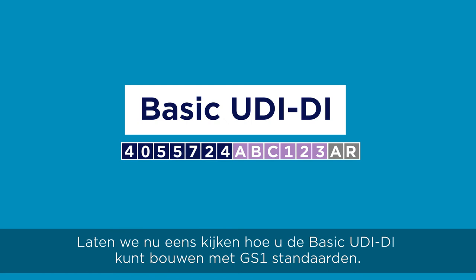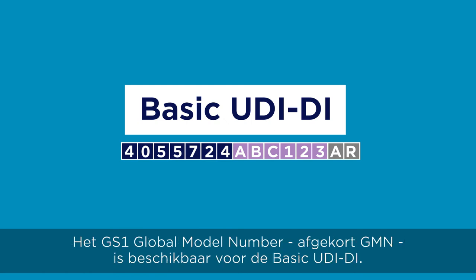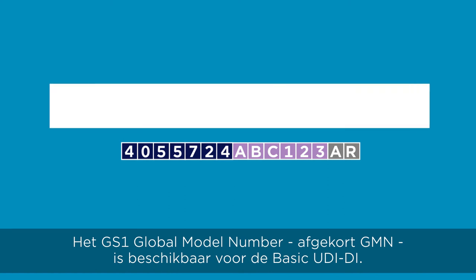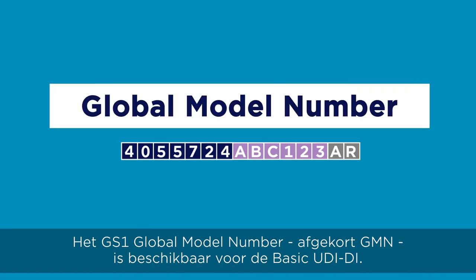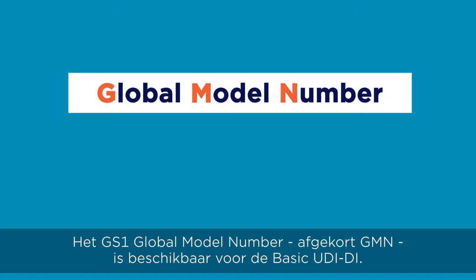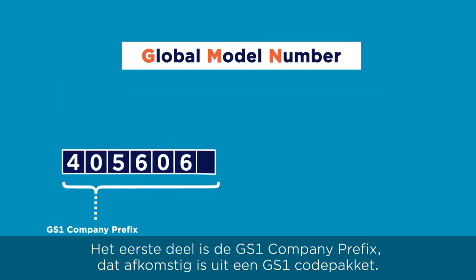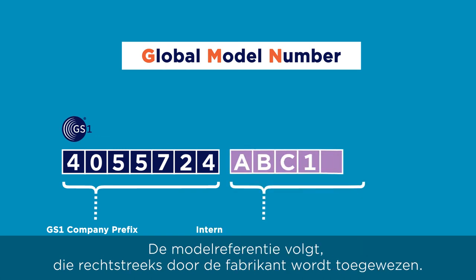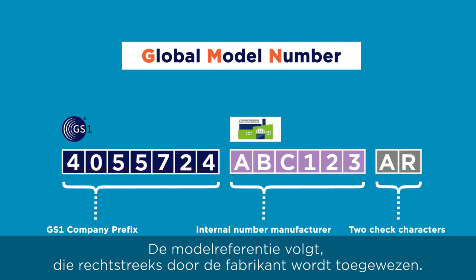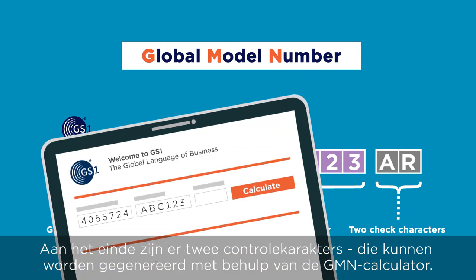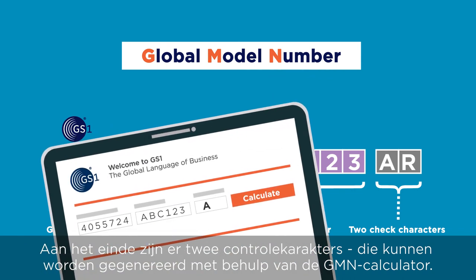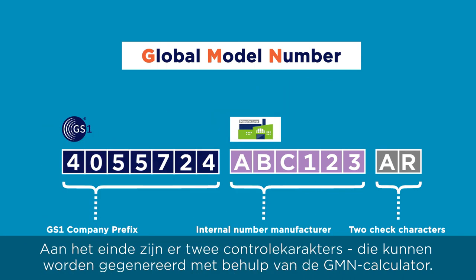Now let's see how you can build the basic UDI-DI with GS1 standards. The GS1 global model number, abbreviated GMN, is a GS1 key which allows the creation of a basic UDI-DI. The first part is the GS1 company prefix, which is uniquely assigned to a GS1 member company. The manufacturer internal number for that group of devices follows, which is assigned directly by the manufacturer. At the end of the GMN there are two check characters, which can be generated using the GMN calculator.